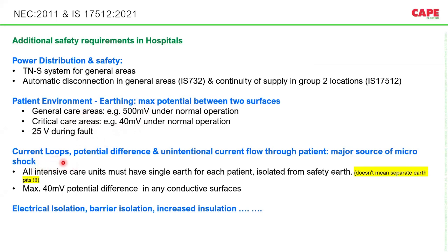The next part is current loop. Potential differences and unintentional current flow through the patient. So this is actually a serious issue in a hospital. Here, what you should do is all intensive care units must have a single earth for each patient, isolated from safety earth. So this is actually a system which is recommended for hospitals.